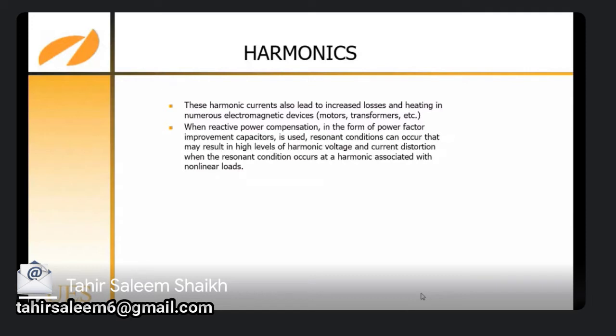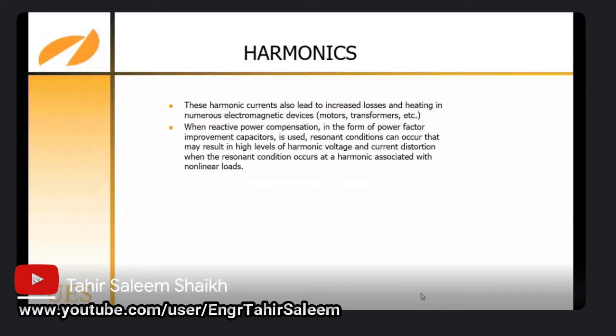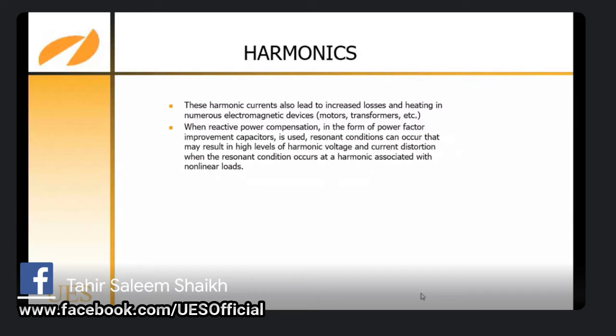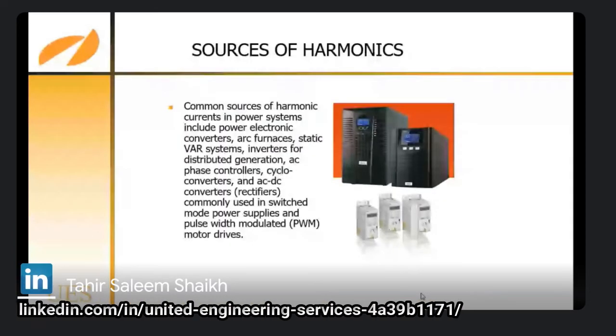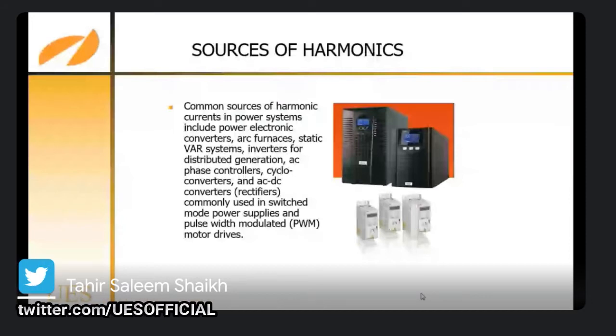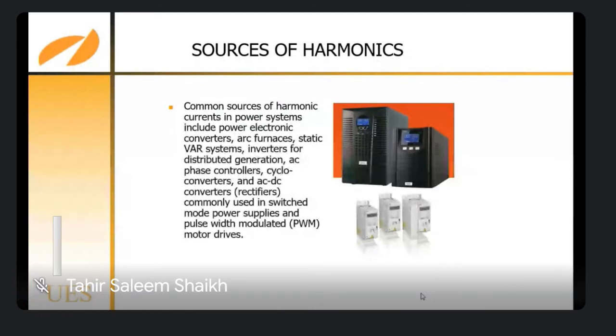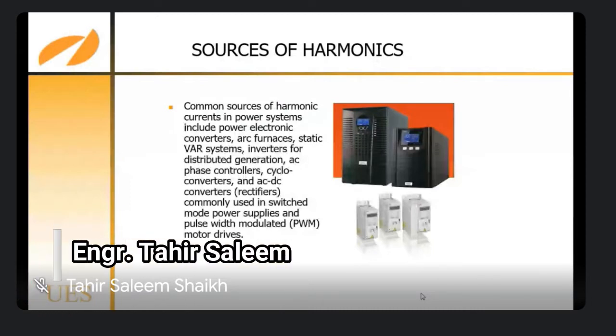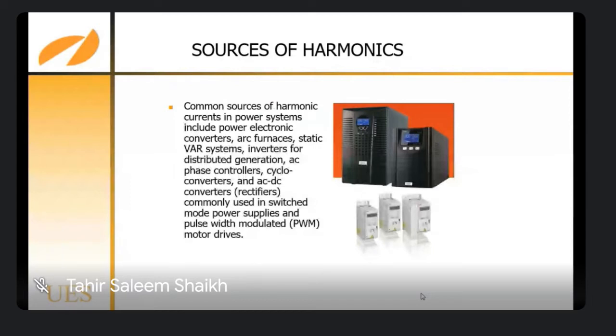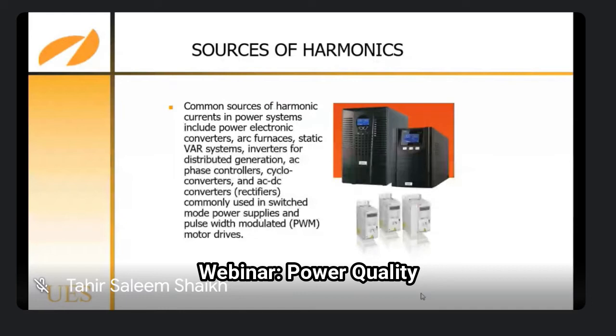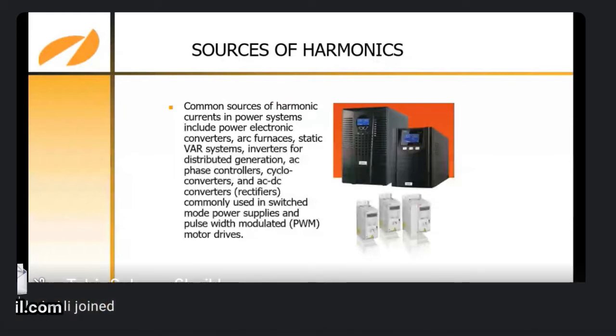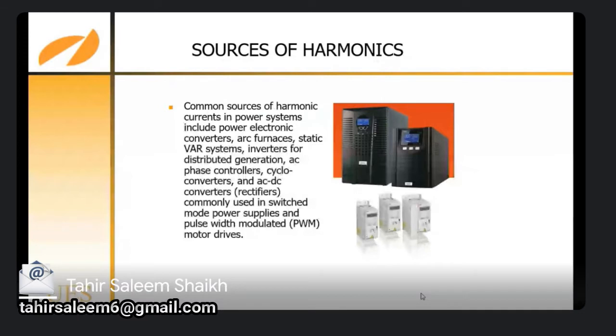Common sources of harmonic current in power systems include power electronic converters, arc furnaces, static var systems, inverters for distributed generation, AC phase controllers, cycloconverters and AC-DC converters, commonly used in switch mode power supplies and pulse width modulated PWM motor drives. The effect of harmonics in a power system is pervasive in that they influence system losses, system operation and system performance. Unless the harmonics are controlled to acceptable limits, the power equipment, and even more so the electronic equipment, may be damaged, resulting in costly system outage.